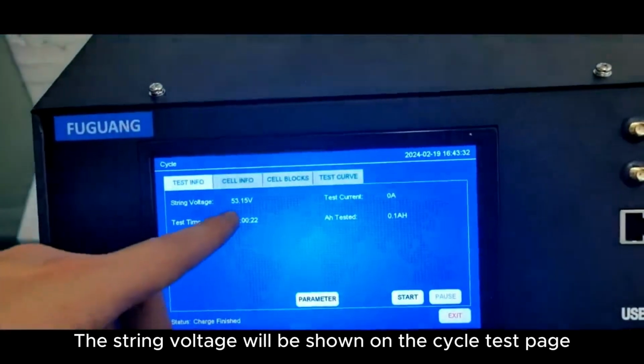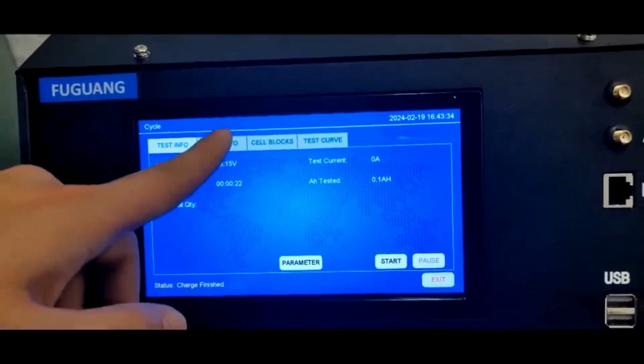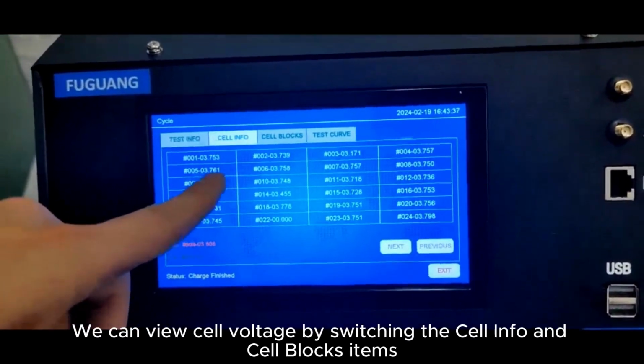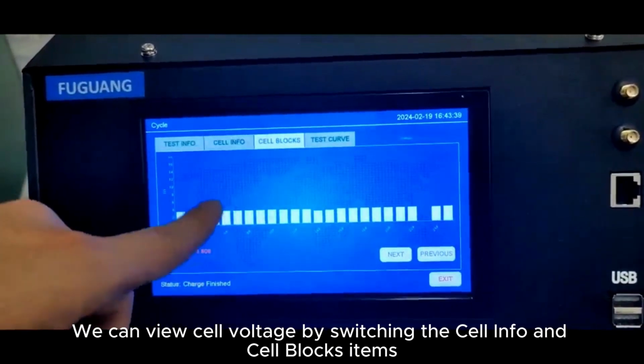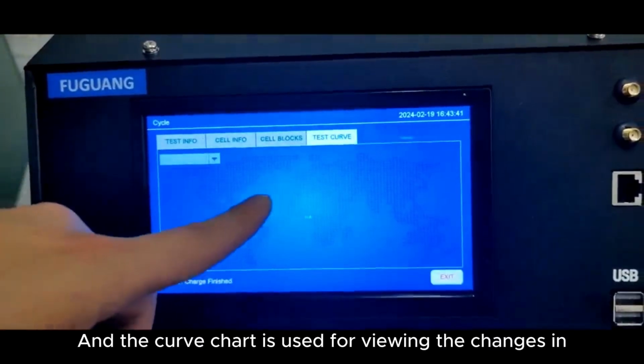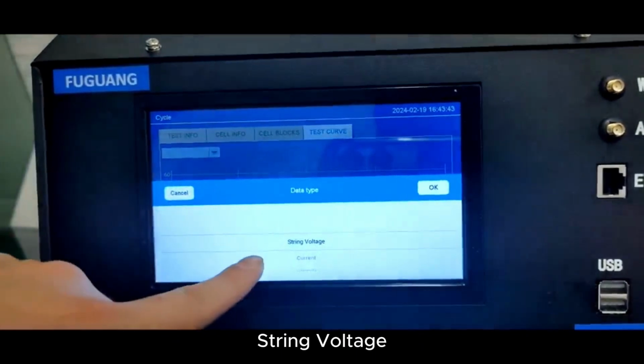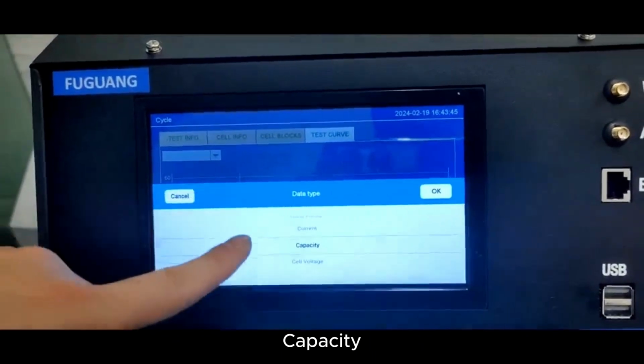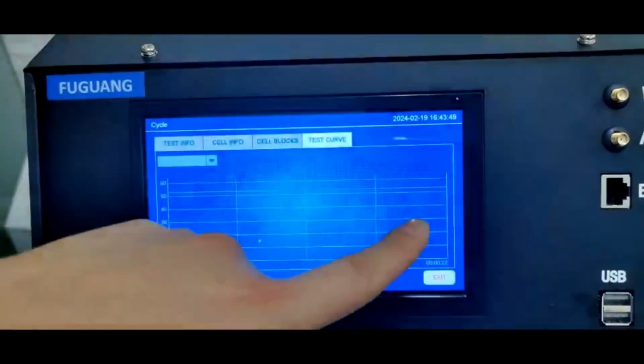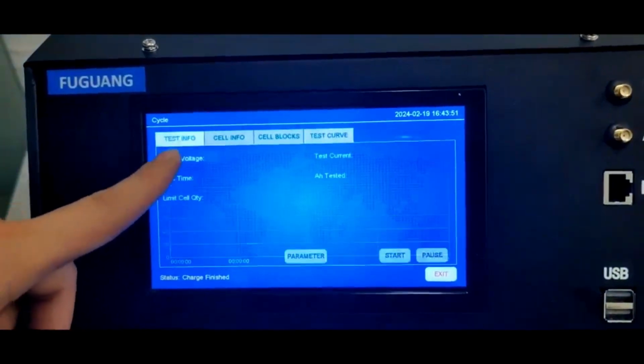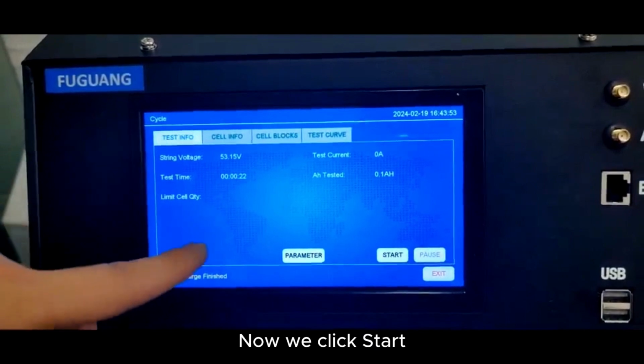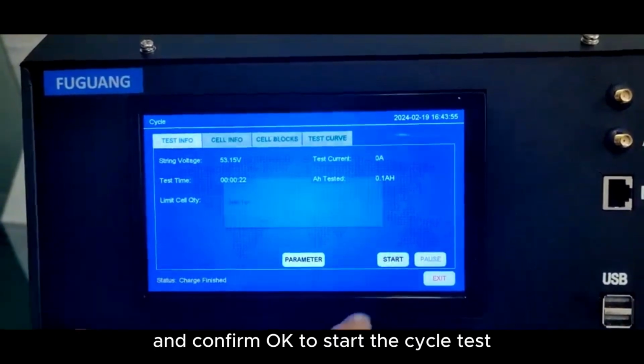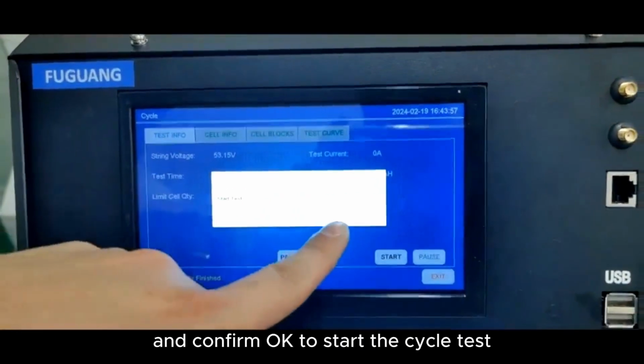The string voltage will be shown on the cycle test page. We can view cell voltage by switching the cell info and cell blocks items. And the curve charts is used for viewing the changes in string voltage, current, capacity, and cell voltage. Now we click Start and confirm OK to start the cycle test.